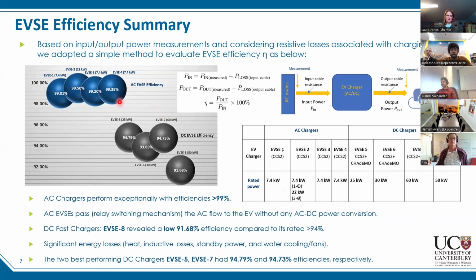Based on the input and output power measurements, and also considering resistive losses associated with charging cables, we adopted a simple method to evaluate the efficiencies. When power was monitored close to the AC mains end, we subtracted the power loss in the input cable. When output power was recorded close to the EV end, we added that extra loss in the cable. So knowing P out and P in values, we simply determine the efficiencies.